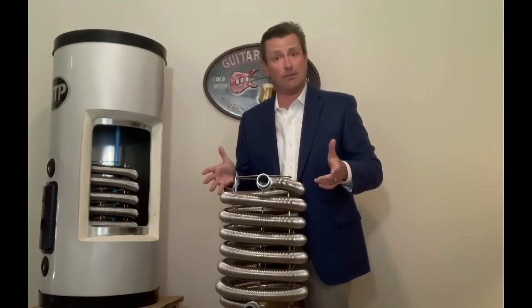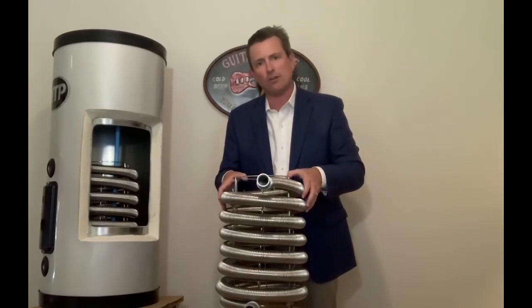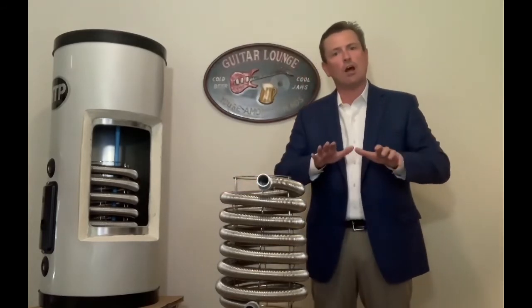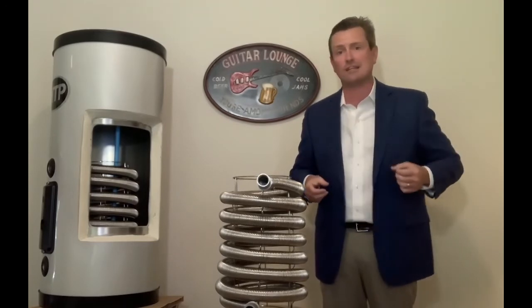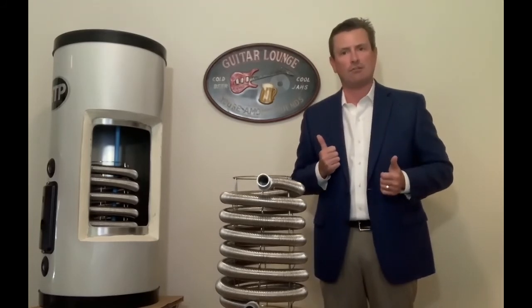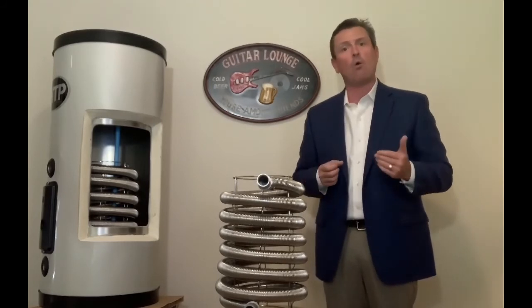What's also pretty exciting about this is because of the size of this 15 square foot surface area heat exchanger, I can actually run lower water temperatures to my heat exchanger and still get really good outputs. Now, what would be the benefit of running a lower supply water temperature to a heat exchanger? What type of boiler would benefit from that? And the answer is condensing technology. We know that condensing boilers don't condense unless they have a return water temperature below 135 degrees. And what we found with the SuperFlex heat exchanger, because of its efficiency, because of its size, is we can lower the water temperature down to around 155, 160 degrees, which allows us to come back below that point in which the boiler can condense, and we can still provide adequate domestic hot water for most applications. This allows me to create a truly high efficient system.